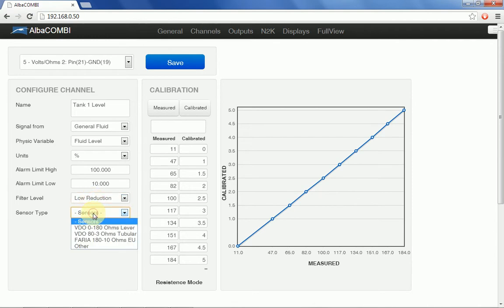Now for sensors. When I've selected a signal, which is fluid, the sensor basically has an analog signal coming from the input, which is fluid, and the channel is configured in resistance mode. With that, the system, if I press sensor, presents me with a few options.